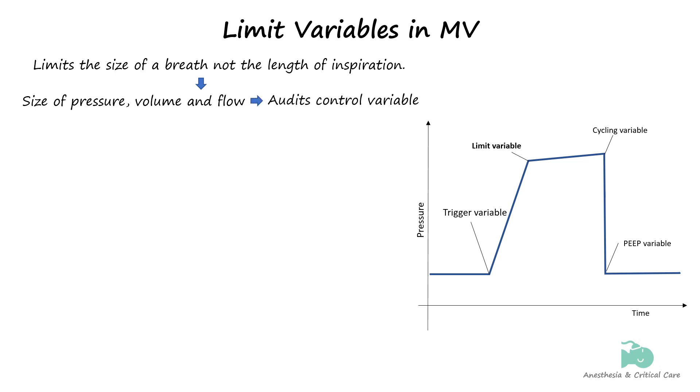Control variables are parameters that the clinicians aim to achieve during the breath. For instance, during volume control ventilation, the clinician sets a tidal volume as a control variable. The ventilator will make sure that the patient receives the set tidal volume, but doing so might also increase the pressure. Limit variable is set to make sure that the pressure is also kept in check.